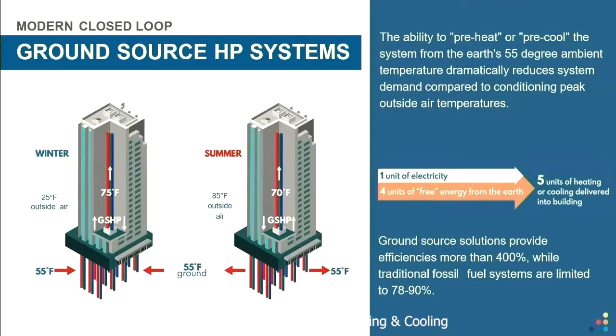We like to say air source systems are really good, but ground source is better. This illustrates that during peak heating conditions in the wintertime, air source systems are getting their heat from a 25-degree source. The ground is generally about 30 degrees warmer than that. And in the summertime, air source heat pumps are rejecting heat to warm conditions outside, about 85 degrees in the summer. And conversely, in the summertime, the ground is much cooler, so it's easier to dissipate heat to the ground. So there's a large mechanical advantage.